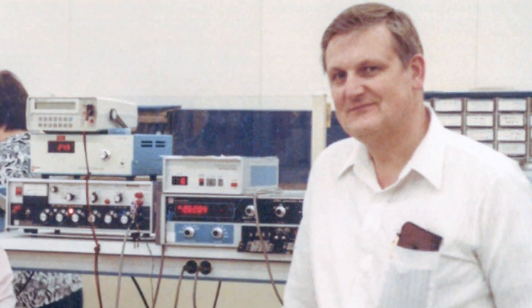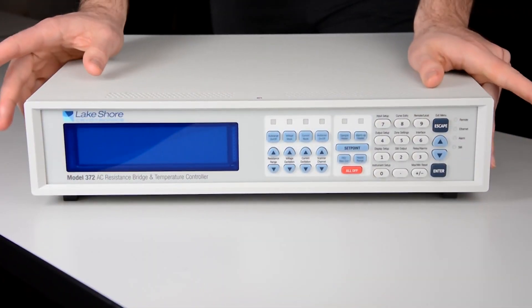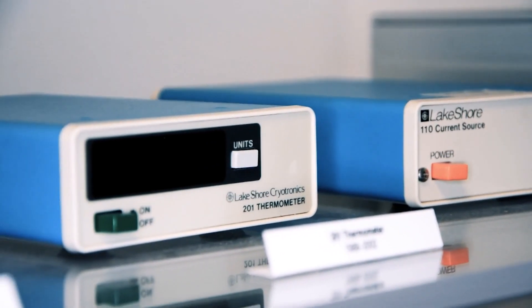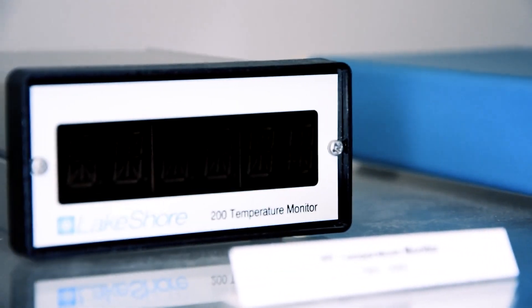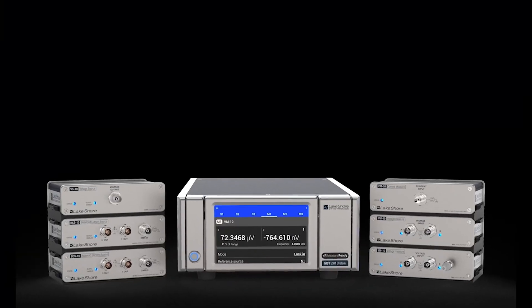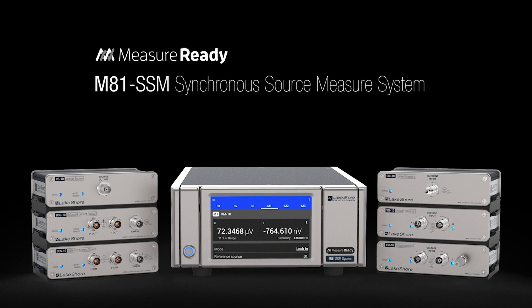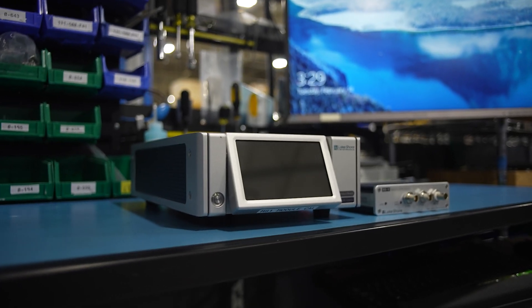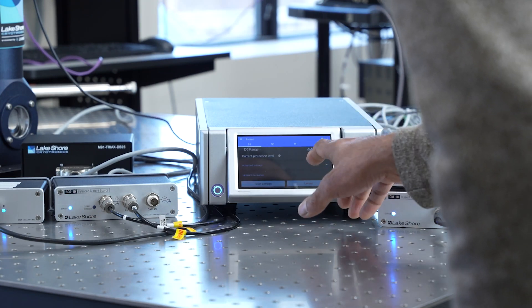Lake Shore has a long history in making low-level measurements of temperature in cryostats and other cryogenic equipment. Those sensor applications and measurements require very low noise, very sensitive circuitry, which was used in the design and development of the M81 to enable a more general-purpose solution optimized for best possible noise performance for cryogenic and other low-level applications.